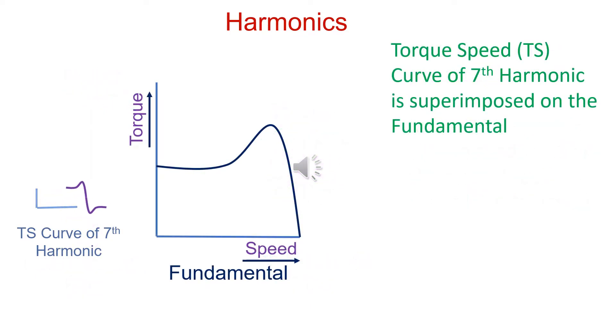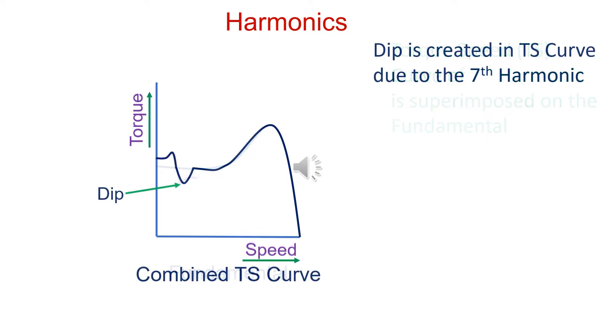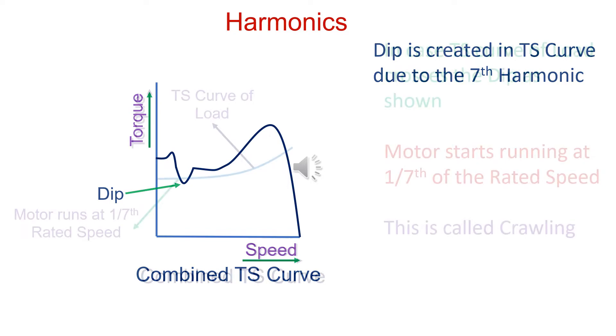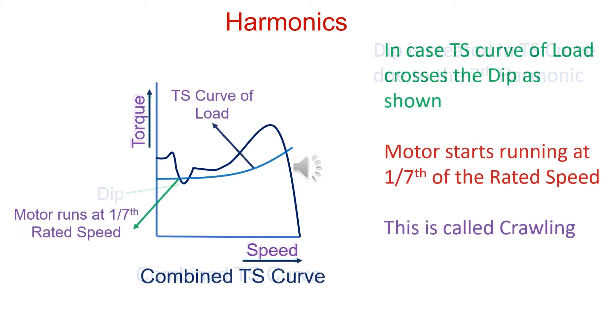The seventh harmonic is superimposed on the torque-speed curve of the motor. A dip is created on the torque-speed curve of the motor. Suppose the load curve crosses the dip. The speed of the motor won't go beyond one-seventh the rated speed. This is called crawling.